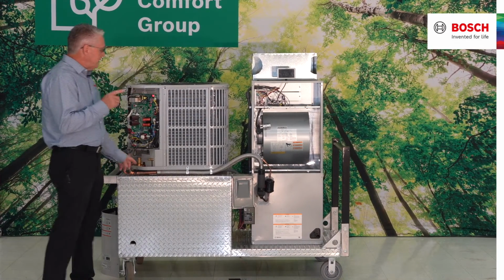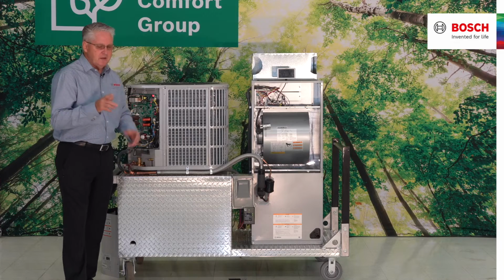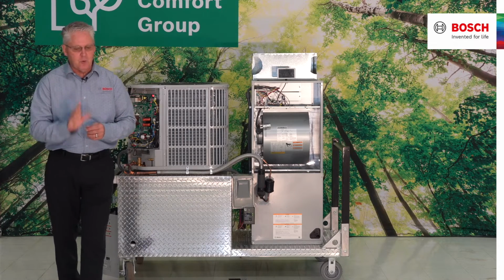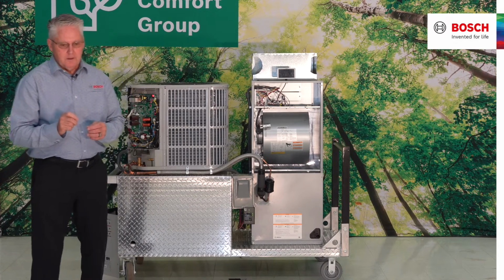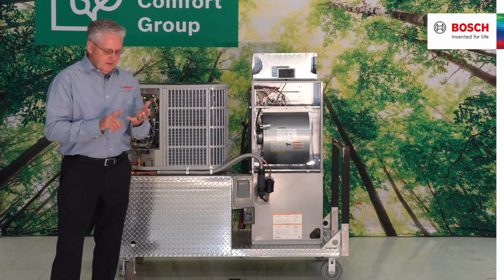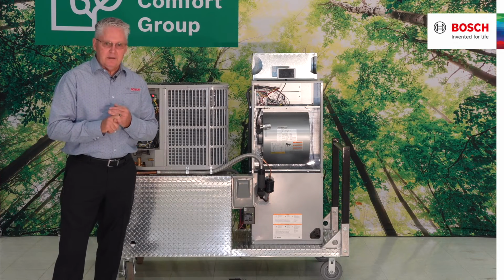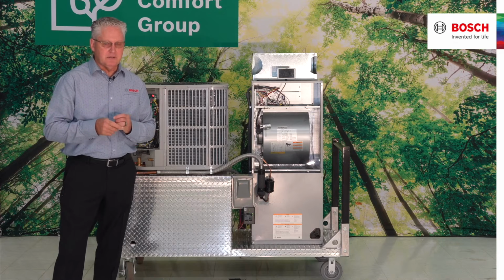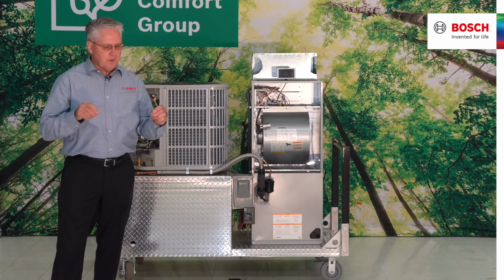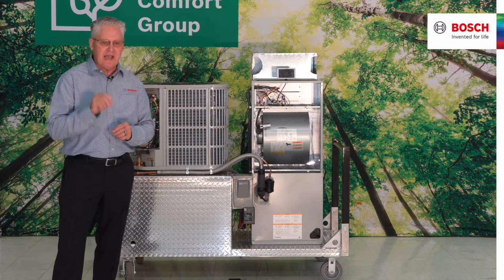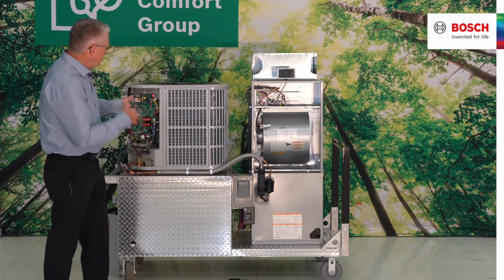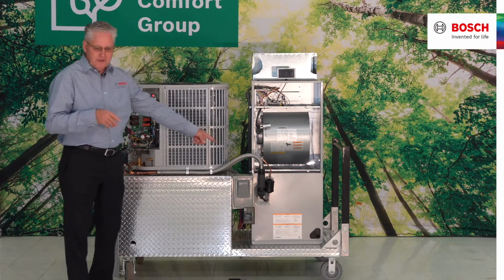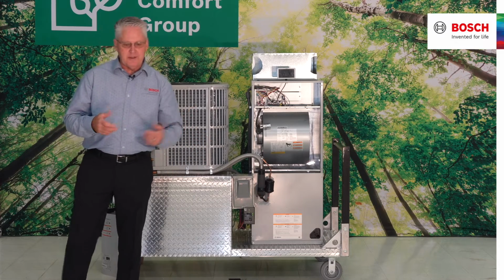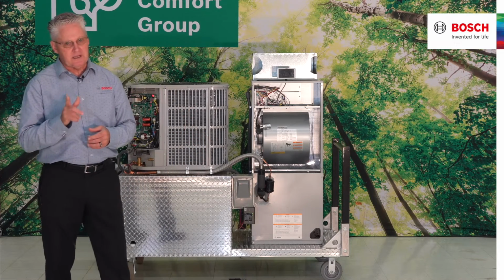One of the characteristics about the refrigerant lines that you need to make sure you always remember: the liquid line has to be 3/8. There is no deviation, it has to be 3/8. All of my units come with the dryer. It is a biflow dryer because you remember that my condensing unit is also a heat pump.